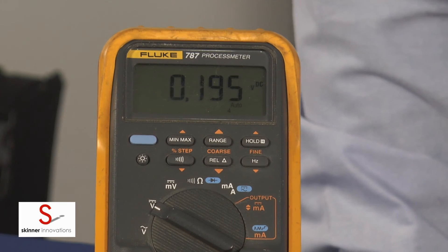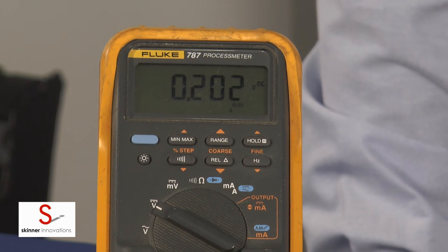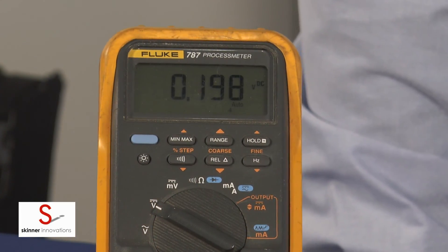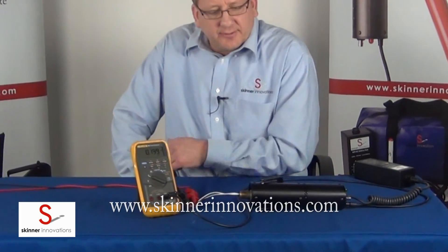Okay, last trip was at 190 degrees Fahrenheit. The temperature will now rise up to its high set point and it will stay there until you either turn off the tester or until the internal safety timer times out and turns off the heat automatically. That concludes our test of the 190 degree Fenwal rate compensated heat detector. Thanks for watching.